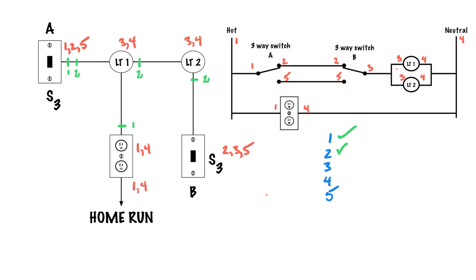Three: I have a three at light 1, a three at light 2, and a three at switch B. So I'm taking the threes just from the switch to light 1 and to light 2. There's no three on the switch A side or down at the receptacle, so I don't have to carry that through. Three and three — check mark, three is taken care of.